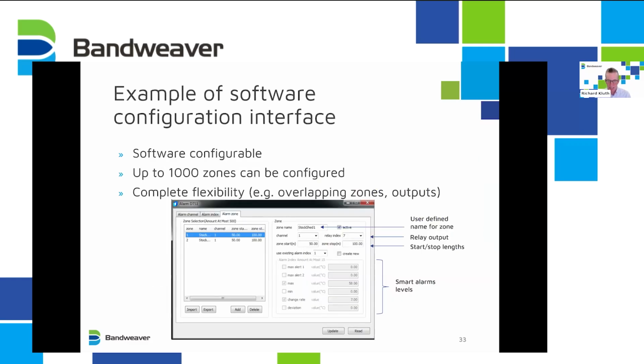You program these in the alarms. This is an example of our software interface. As I said, you can do 1,000 zones, you can overlap them, you can change the output, which relay, where it starts, where it finishes. Each zone can have a number of different alarms. So you've got ultimate flexibility in how you want to do that. A lot of people set zones to be quite similar, but in some cases some zones are quite abnormal, so it gives you the flexibility to do both.